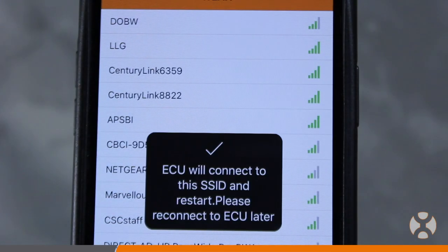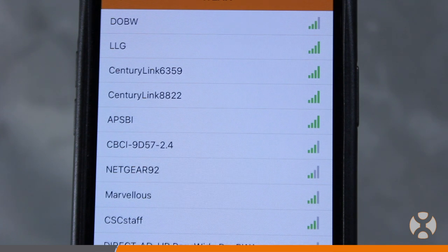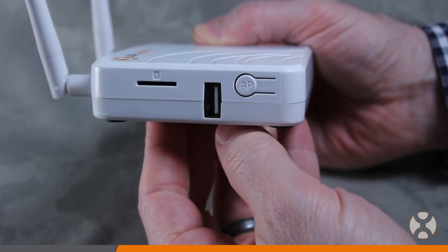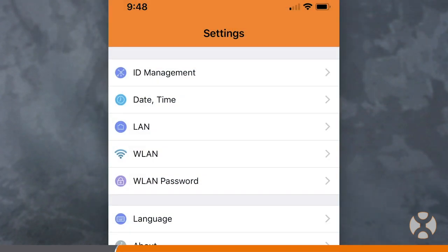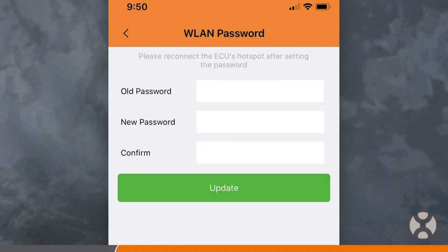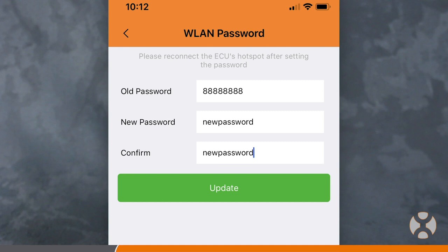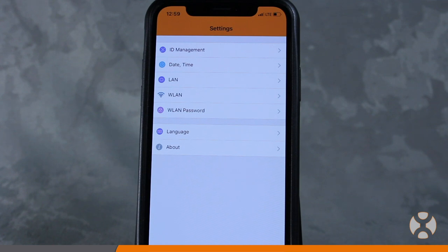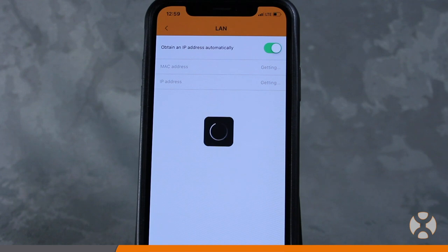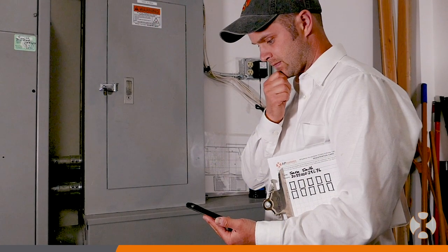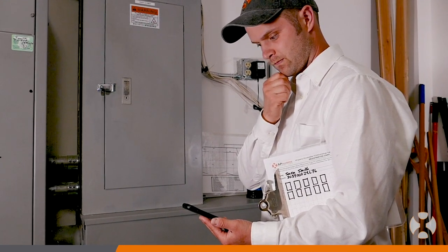You may need to obtain this wireless password from the home or site owner. Please note that once this operation is complete, the ECU may reboot — you may also need to reconnect to the ECU after it reboots and press the AP button again to enable connectivity to your smartphone. Under the WLAN settings, you'll have the option of changing the hotspot password used to connect your phone to the ECU: enter the old password, which is eight 8s, and provide a new one to keep in your company records. The LAN or wired network setting has two options: automatically obtain an IP address, which is the default setting, or choose a fixed IP address with user-specified settings — this second option is only recommended for installation professionals familiar with these settings.